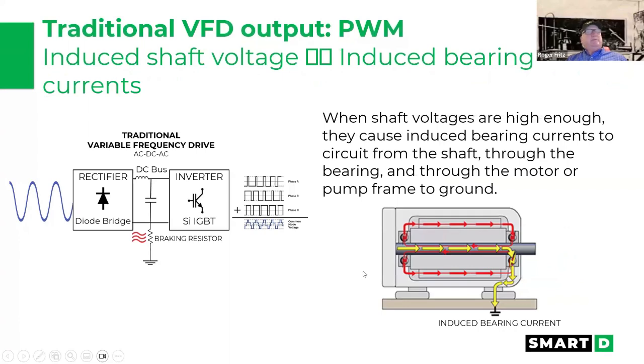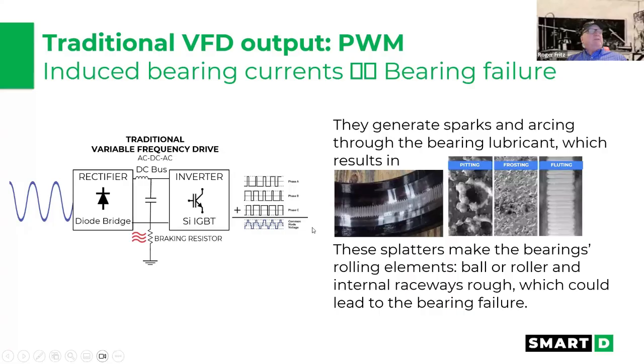So let's talk about the grounding. And this gives an idea of what happens over time. This happens to be the inside of a bearing, and it starts creating pitting, frosting, and fluting. Over a period of time, there've been several guys that we've run into where they have long lead lengths, and in mines and such, they can't have this. So they end up going in and changing the bearings out all the time. They're trying everything possible to eliminate those bearing failures. And a lot of people didn't know it until after about 3, 4, 5 years, and all of a sudden the motor started failing prematurely.